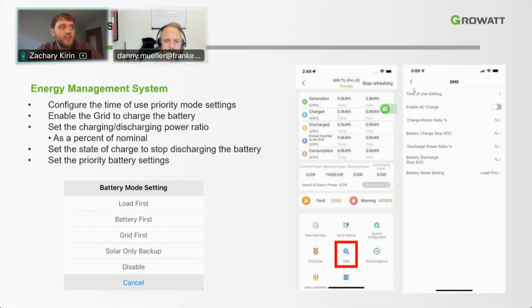Enabling AC charge just allows the inverter to run and charge the battery at its maximum power, even if it has to do so with the grid. So enabling AC charge will allow the grid to charge the battery. And then you can set the various means of charging power here. You can set stop and start ratios and the battery mode setting, of course. These are the different battery mode settings that are available.